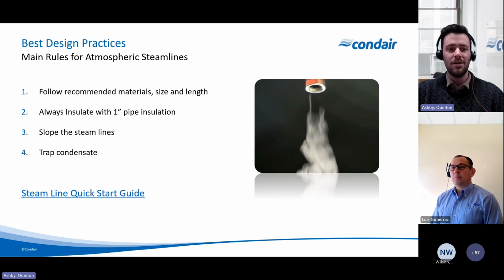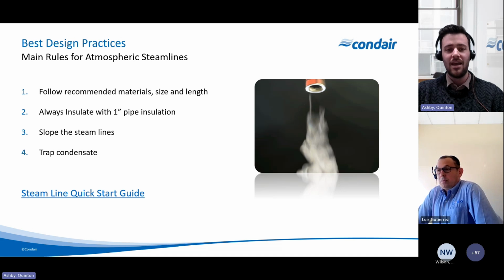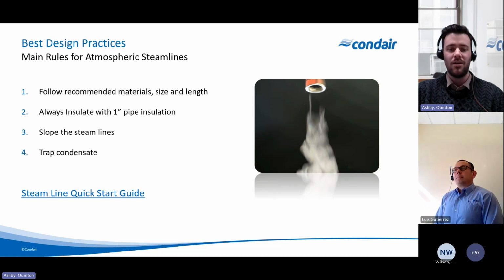For number 2, we always want to make sure that we're insulating the pipes itself. So as this is atmospheric steam, if there's a lot of conductivity and a lot of heat transfer within the pipe, we can actually start to lose it to condensate, which I'll go over in a little bit. So we always want to make sure we're insulating. 3, steam lines always have to be sloped. So we're getting rid of the condensate via gravity. So if you have a flat line, that can actually start to impede the steam itself. So we want to be really careful when we're installing steam lines that they're always sloped, and we want to consider that when we're looking at possible installation requirements.